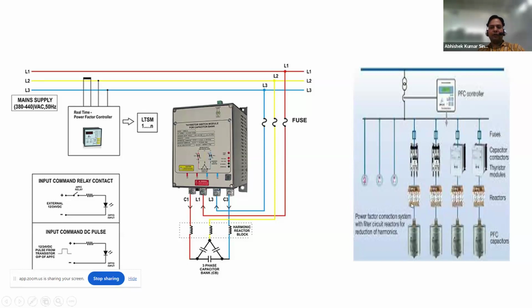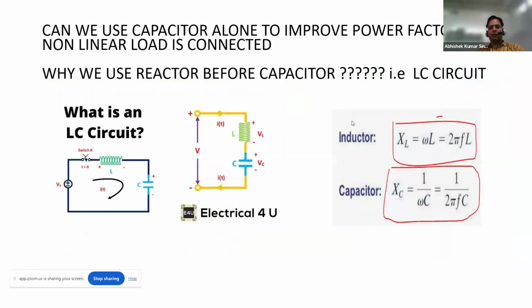What is the use of having a reactor here? As we discussed earlier, the reactor is placed before the capacitor. So why do we use a reactor before a capacitor? XL is equal to omega L, which is equal to 2 pi FL, and XC is equal to 1 upon omega C, which is equal to 1 upon 2 pi FC. So if there are harmonics in the system, say a fifth harmonic, it means 250 hertz. When there is a fifth harmonic, the capacitor reactance will be very low, because it is inversely proportional to frequency. If it is very low and nothing else is in the system, the harmonic current will attack it, and your capacitor will get damaged.